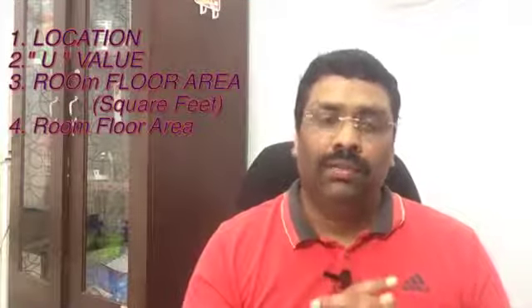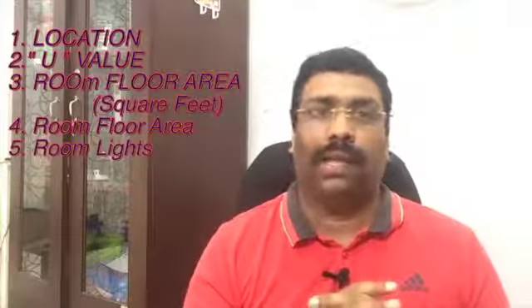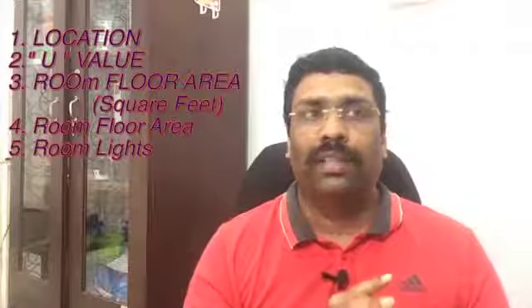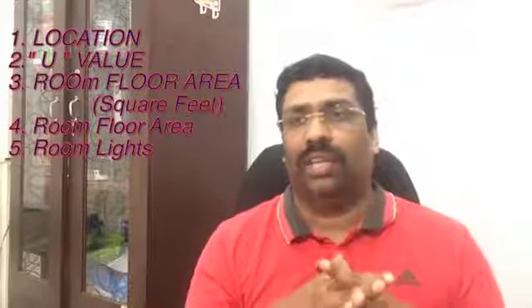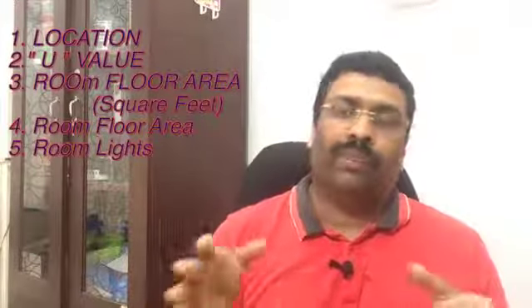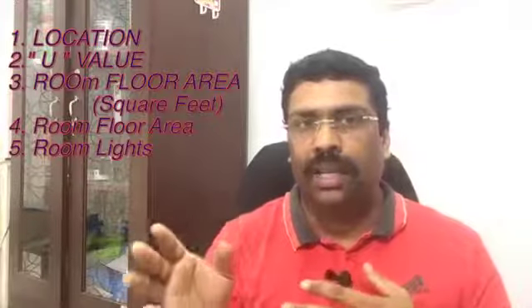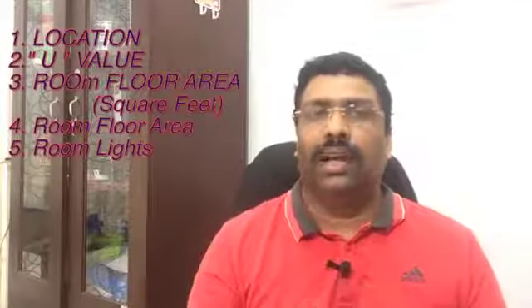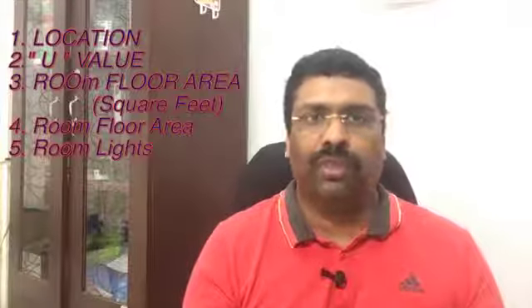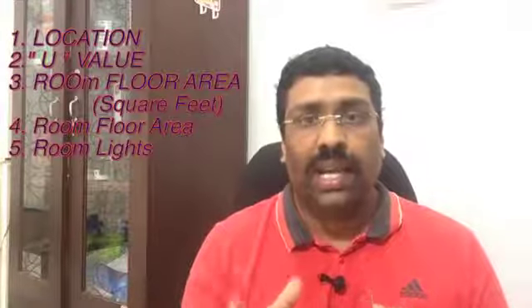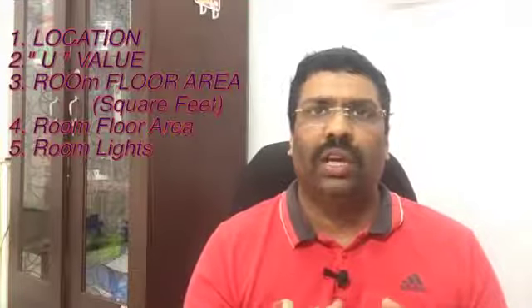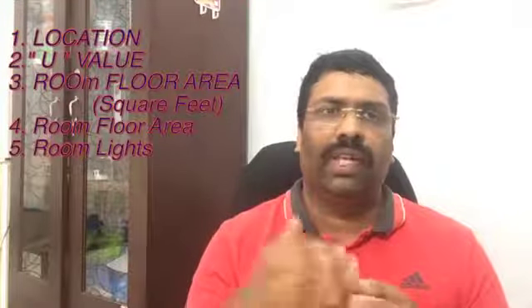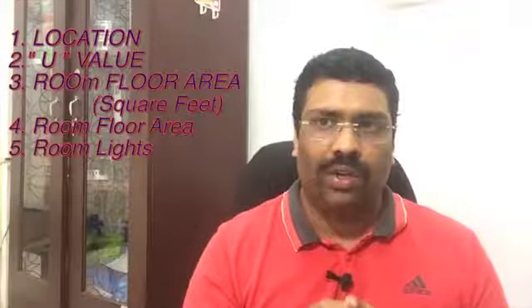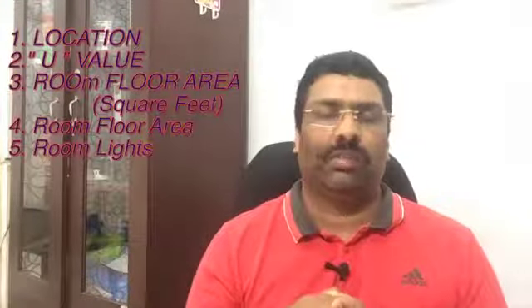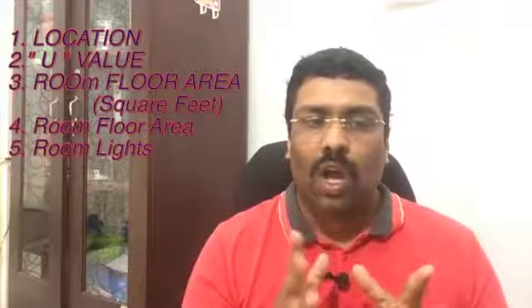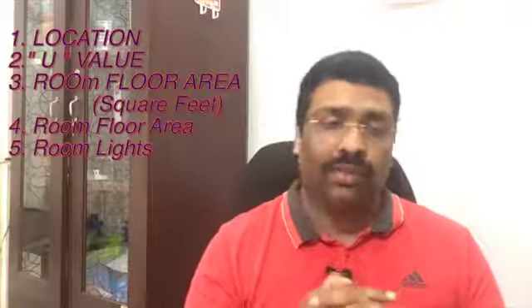The fifth point is room lighting - how many lights are there, any heat generating or halogen type lights. There's already a standard calculation based on square feet, which I'll explain when demonstrating the software - what is the standard calculation for normal office area per square foot in watts. We can put that direct value or measure it. It's very simple, nothing big deal, just how much lighting we have.